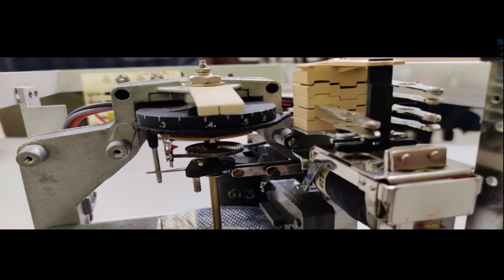Now coming to this one, here you see this is one dial. That dial can be rotated in a clockwise or anti-clockwise manner, and some markings are there. Presently, this one is fixed at, say, 0.44. So using this dial we can control the operating time of the relay. Why do you need to control the operating time? If the current sensed by the relay is more than the current setting value of this particular relay, then the relay should operate and generate a trip signal which will activate the circuit breaker.